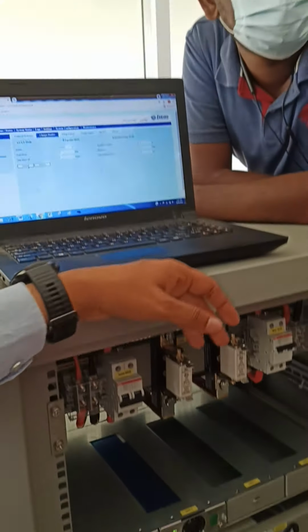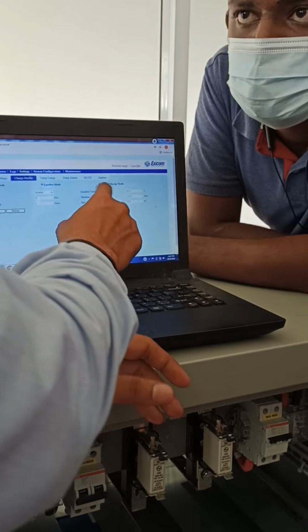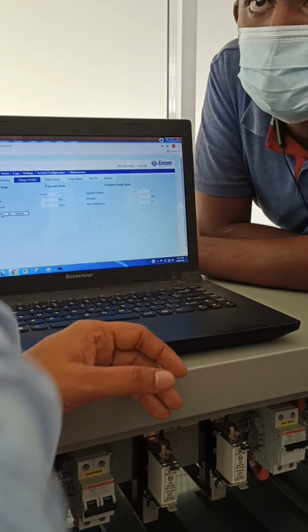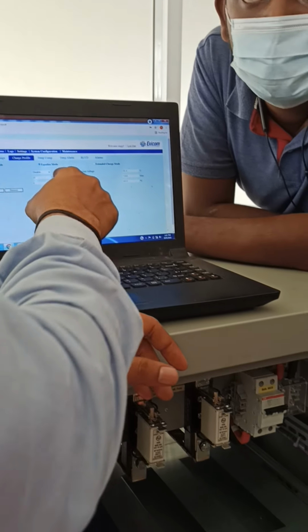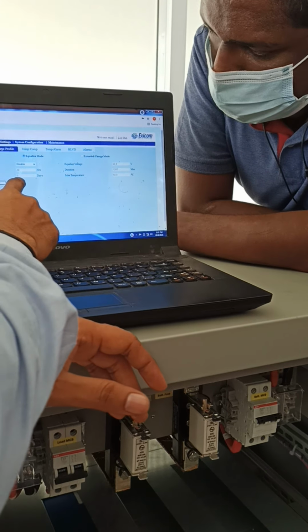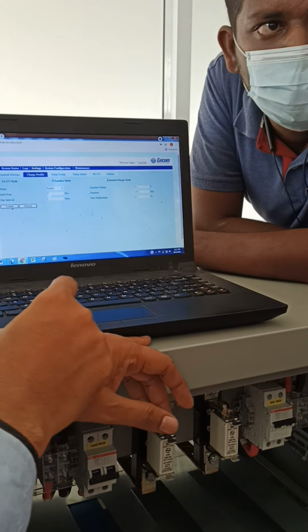First we are setting the day. These changes: we start at 20 hours with a duration of 160 minutes and change the equalization voltage to 56.4. This is done on the first day, the first day of installation. So we do all these things. Then we make the interval zero, disable it and submit. This is on the first day, at the time of commissioning.